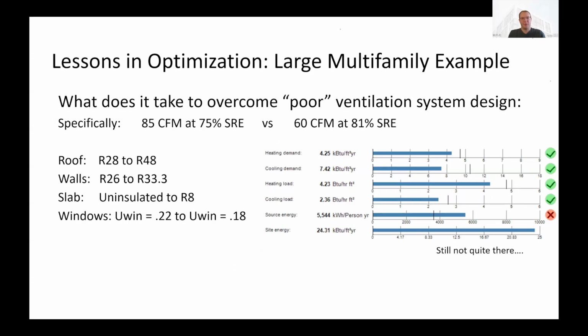And so what does it take to overcome poor ventilation system design? And before I go into this, one reason I chose 60 CFM, not 45, is the engineer was saying on some of the larger units that have multiple bedrooms, we actually will need more airflow for the supply side. And so I think it's more reasonable that we're not going to get down to 45 CFM, that we're going to be closer to 60 CFM for each of these units. And also, I don't mind bumping the bathrooms from 20 to 25 CFM because I think it's going to make balancing these systems easier, rather than trying to meet a minimum. If it measures out at 23, you're still good. So just keeping that in mind, I chose to go with the 60 CFM.